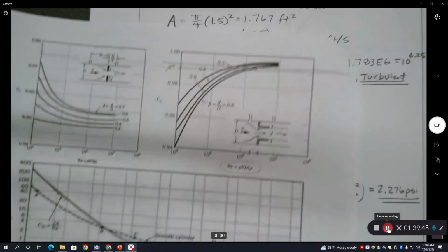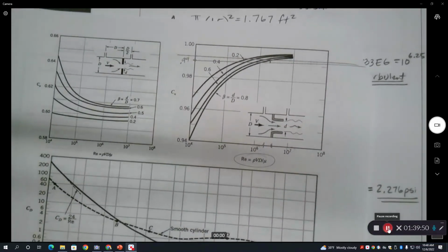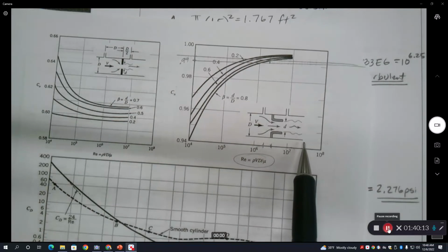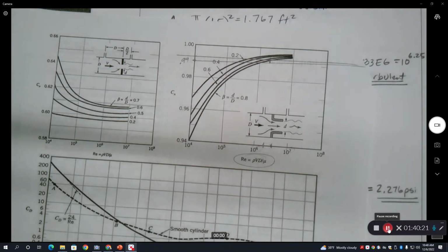So for those nozzle flow meters, going back to earlier, that would cause cavitation because it's increasing velocity, correct? Well, only if it did the velocity too much. Yeah, but would that screw with the flow meter measurement? If it did cavitate, yeah, then it would stop it being effective. Okay. So you would want to design, you just don't want it to get close.